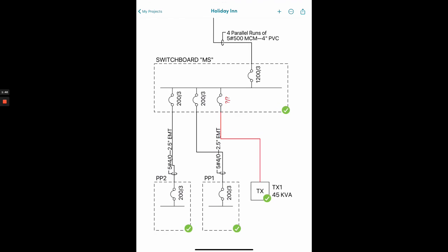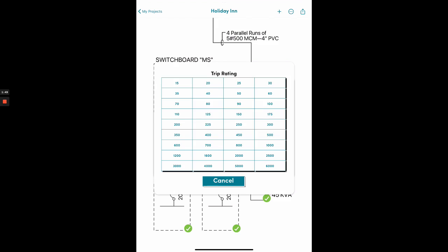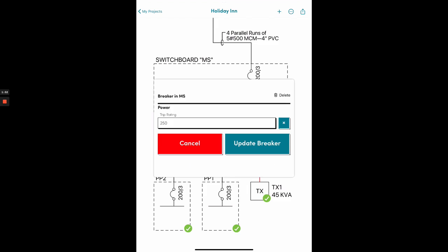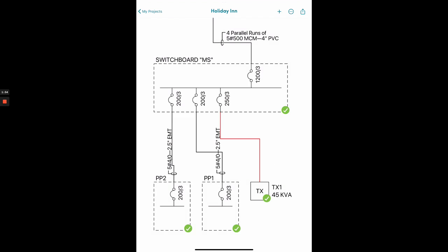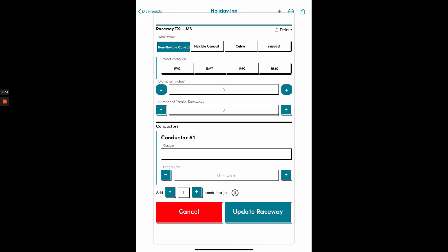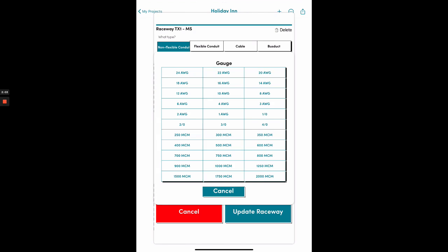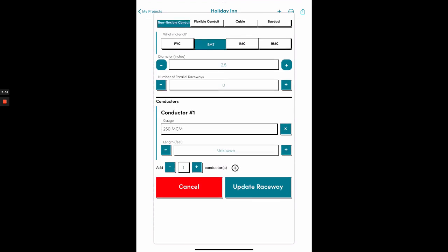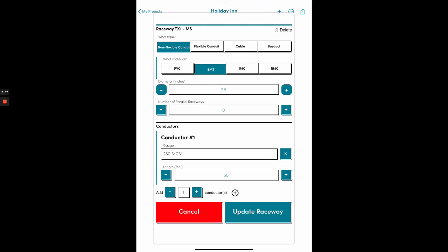And again, we have not put in information about this transformer. So the first thing we're going to do, I'm going to tap the question marks there in the breaker that's in switchboard MS and tell it this is a 250 amp trip rating. Update that breaker, and then tap the raceway and say PVC. Now we'll say it's EMT. We'll say it's 2.5 inches, 250. We'll say it's 250 MCM, 50 feet long. We'll add a few more.